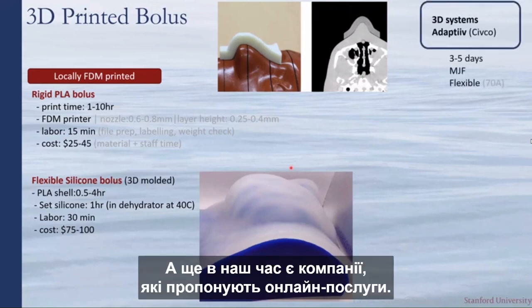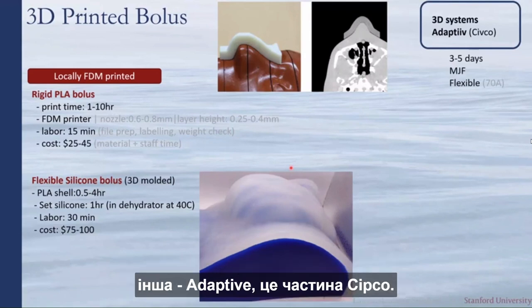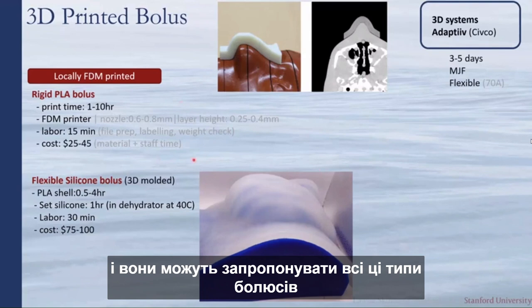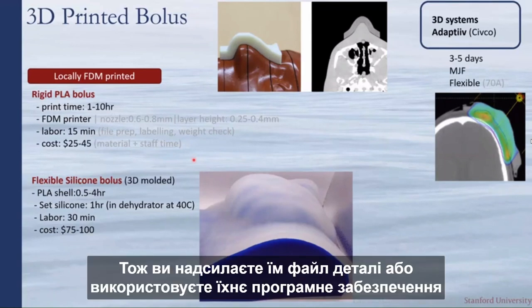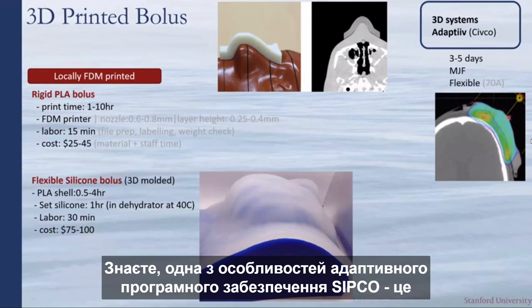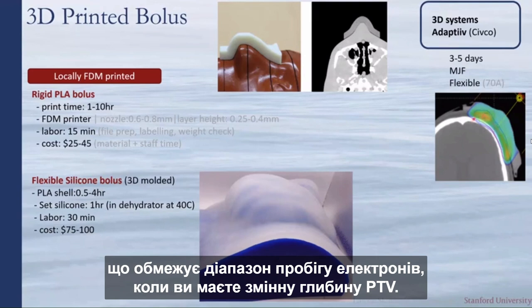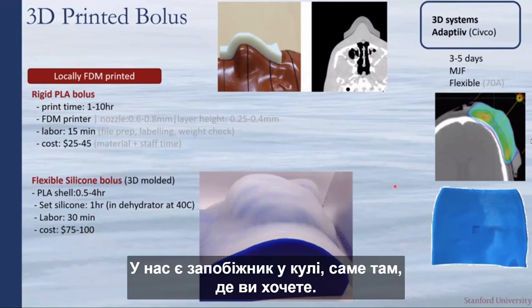Commercial online services such as 3D Systems and Adaptiiv (part of CIVCO) offer approximately three-day lead times for mail-order bolus printing. You send a part file or use their software to generate the geometry. Notably, Adaptiiv's software includes a modulating thickness bolus algorithm that varies bolus thickness to limit the range of electrons where there is variable depth with the PTV.